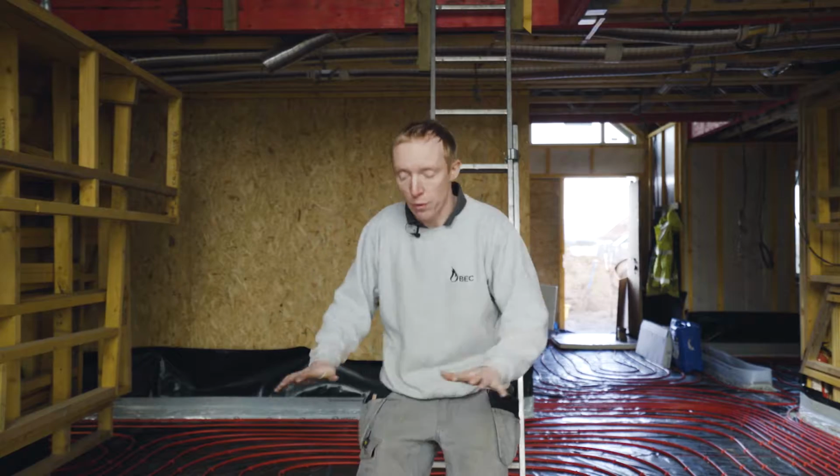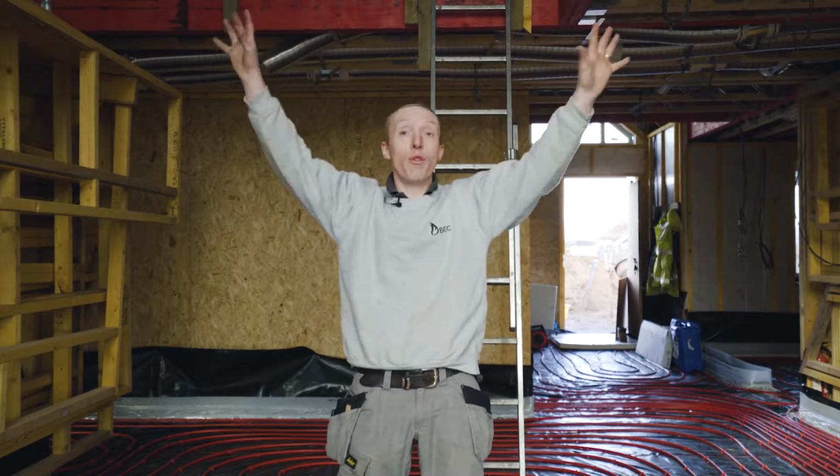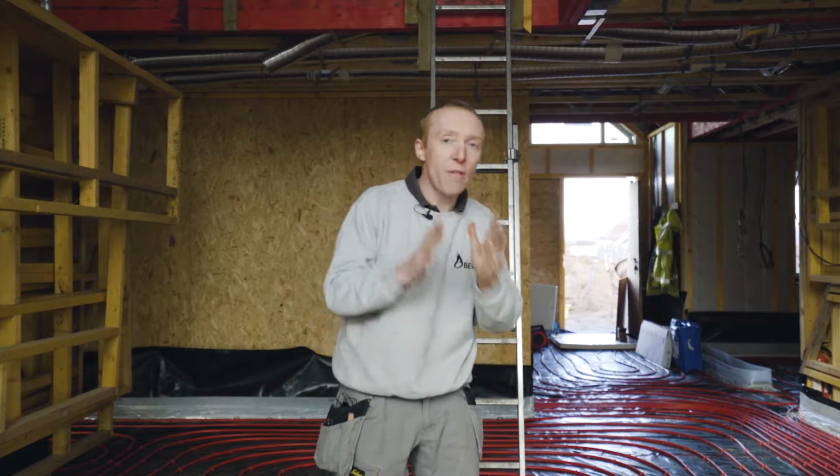And the way to do this is actually very, very simple. What you do is you have to get something called the U values of the property. So the U values of the floor, of the roof, of the ceilings, of the walls will all have a different U value. And then what you've got to do is get the U value, times it by the area of the floor, the walls and the ceiling. And eventually that all gets added up together and gives you one big number.